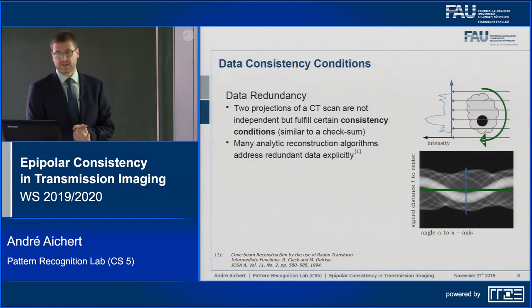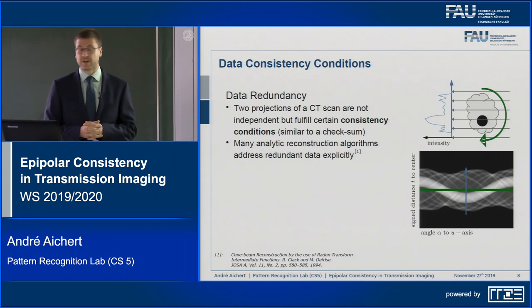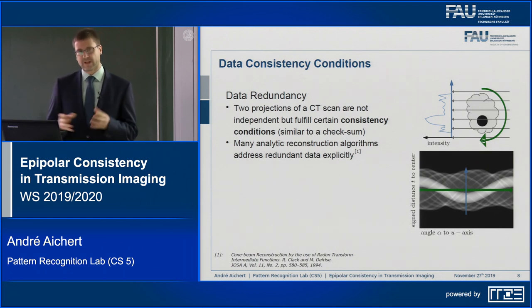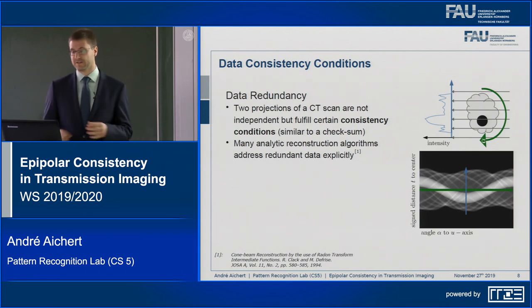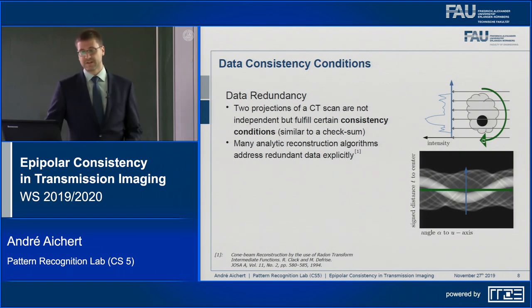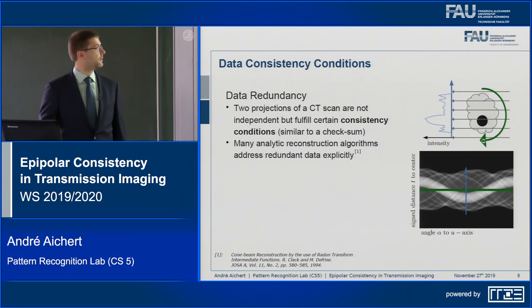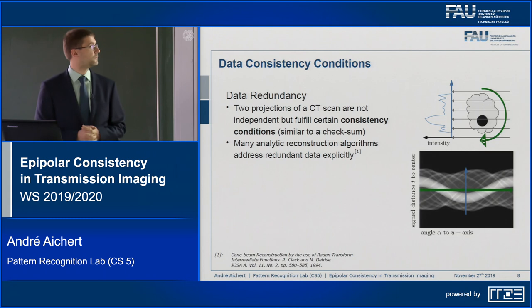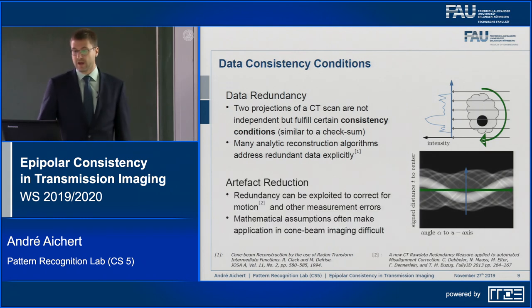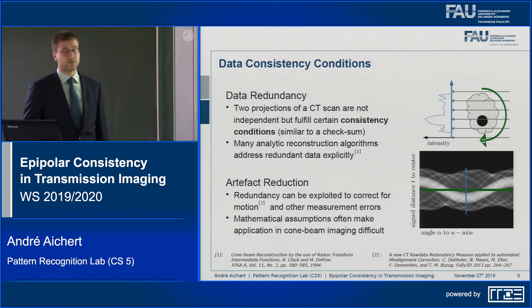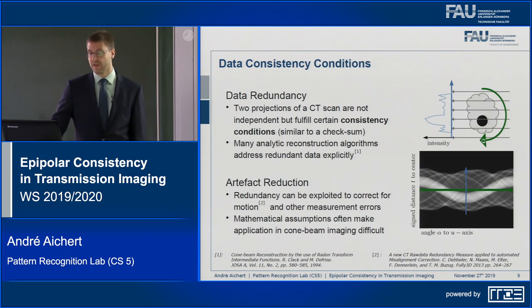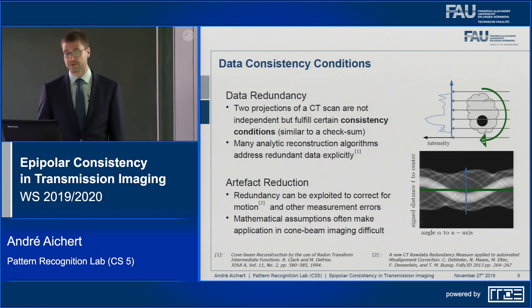To start, I'll briefly define what data consistency conditions are. Two projection images in a CT scan are not independent — they fulfill certain consistency conditions because there is redundant information in both. It's sort of like a checksum: if there is an error in the acquisition or some assumptions are not met, this redundant information will not be exactly identical in the two images. We will be using consistency conditions for artifact reduction and motion estimation in x-ray images.